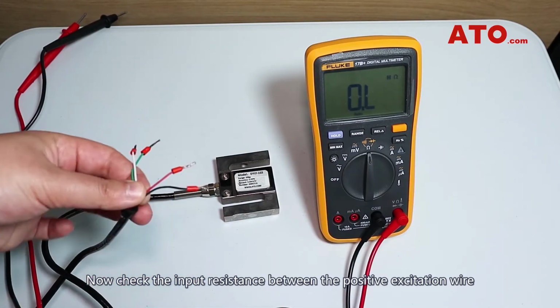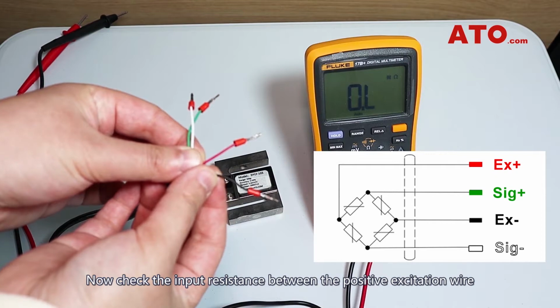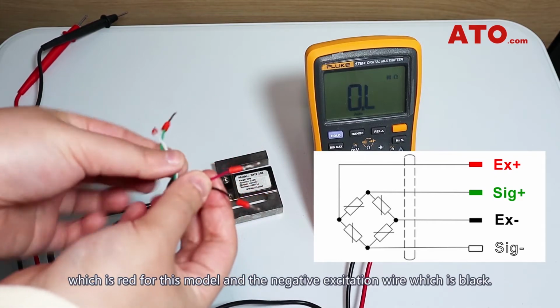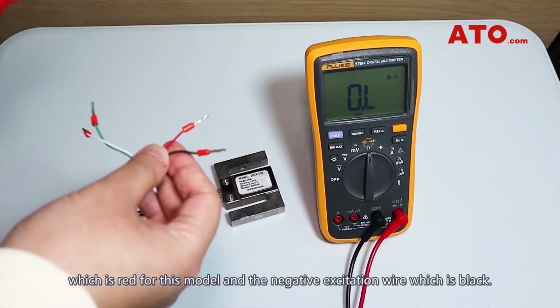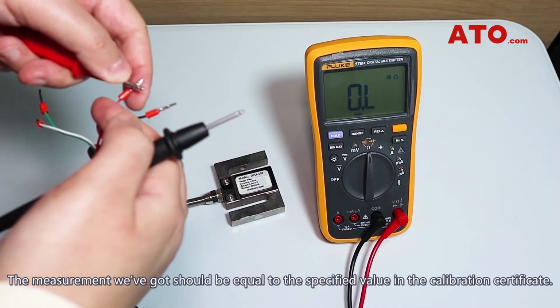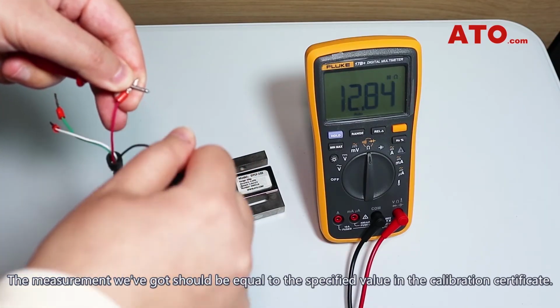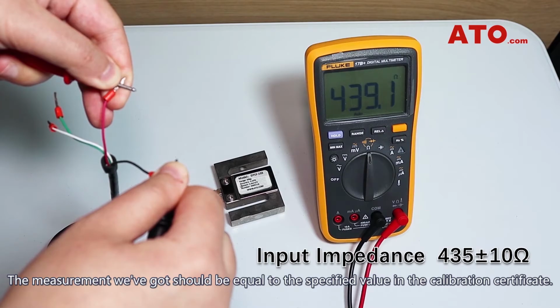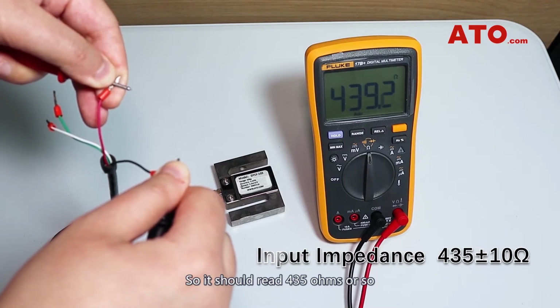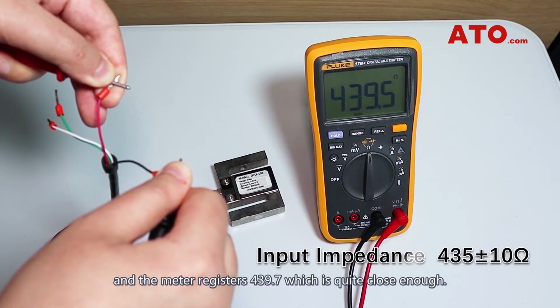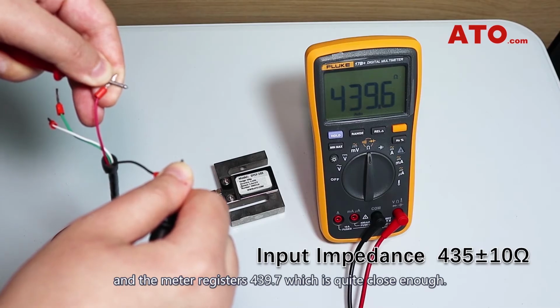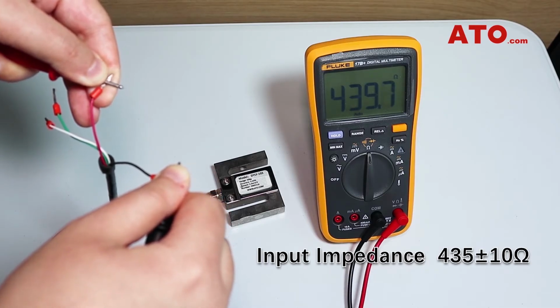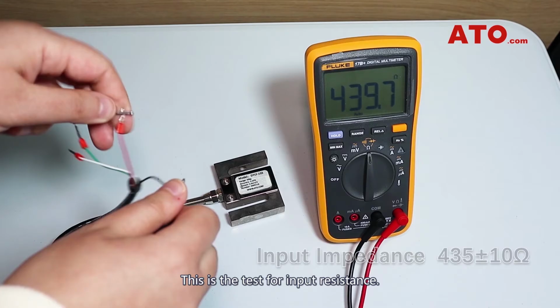Now check the input resistance between the positive excitation wire, which is red for this model, and the negative excitation wire, which is black. The measurement we've got should be equal to the specified value in the calibration certificate. So it should read 435 ohms or so, and the meter registers 439.7, which is quite close enough. This is the test for input resistance.